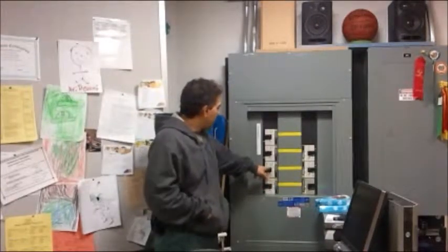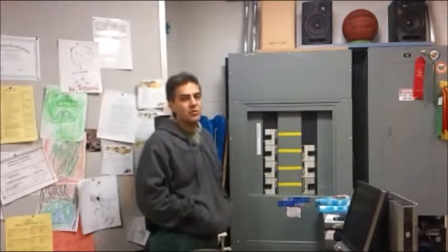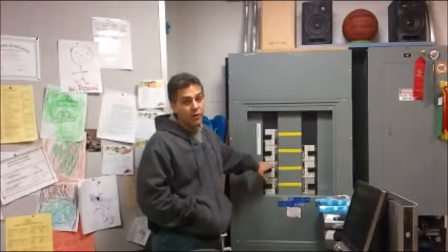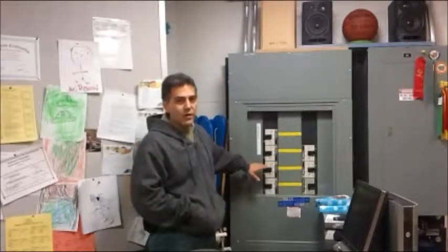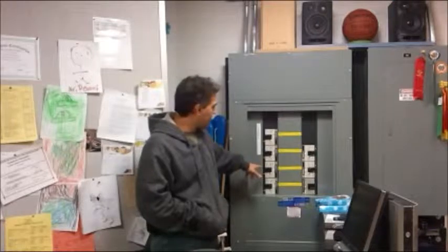And we're going to feed it with a 30 amp breaker. 30 amp breaker is what we're going to need. Again, code-wise, I looked it up. If we go above a certain percentage on the primary, we have to breaker the secondary side of the transformer also. In order for me not to have to breaker the secondary side of the transformer, I would have to actually put a 25 amp breaker in here. These breakers here are very expensive. It's a 480 volt breaker, and I think this here is probably close to $300-400 for this breaker.